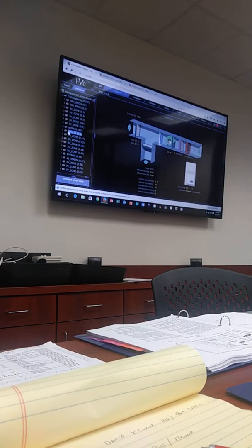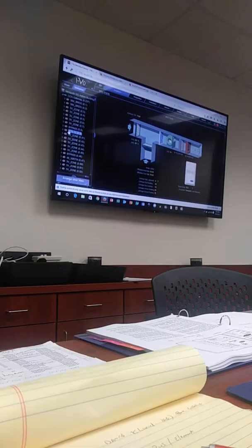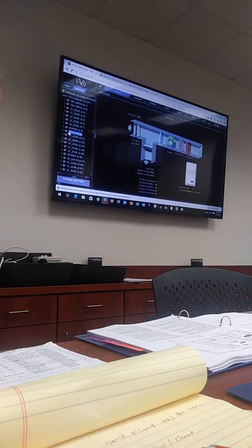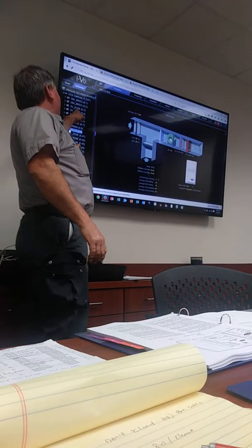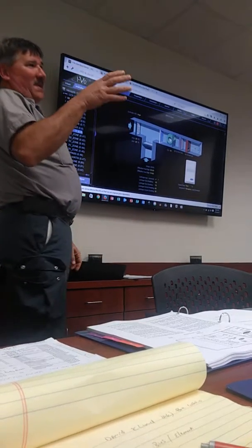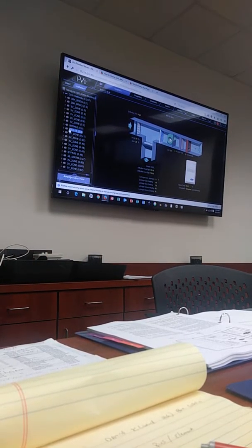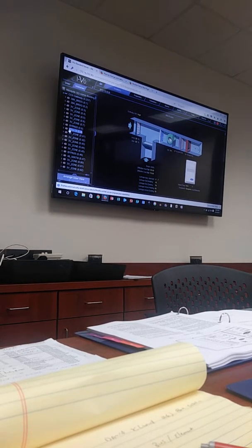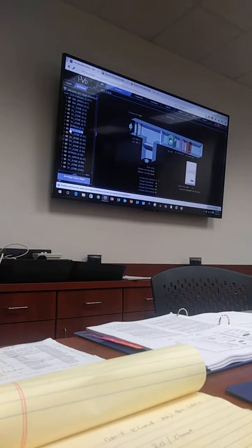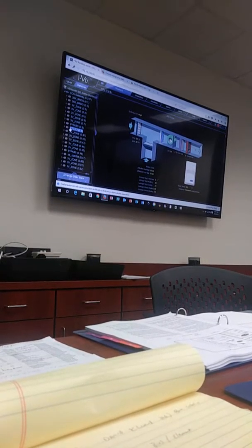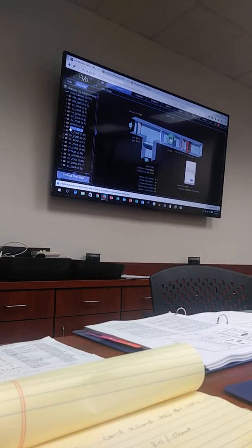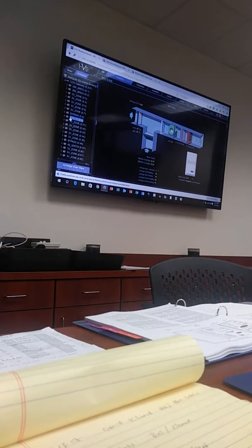Now, in that situation where somebody ducked one of these into a computer room that's going to be calling for cooling nonstop, this system will run, and let's say this is the computer room. It'll run based off its set points and its zone temperature for 1 hour. And if things haven't changed, it's going to kick that guy off to the side and go back to these other guys. Okay, that's good. So if he's off in left field, we're not stuck with one guy forever. But that's really treating the symptom, not the problem. The problem is it should have never been connected to the computer room.